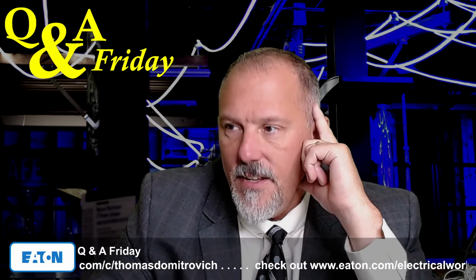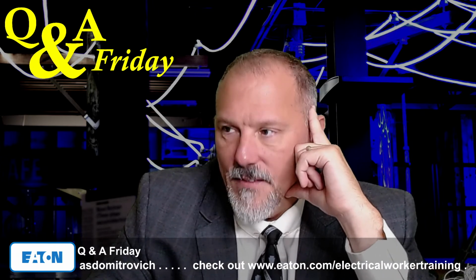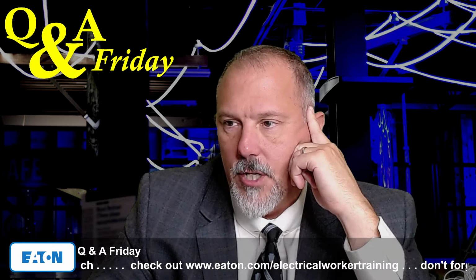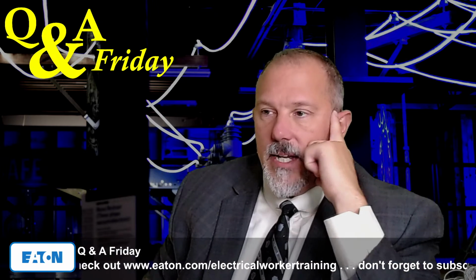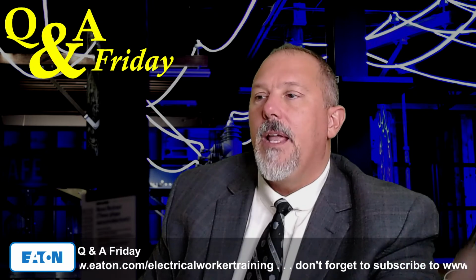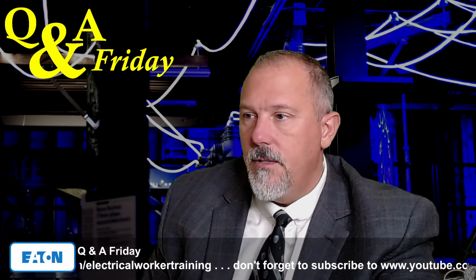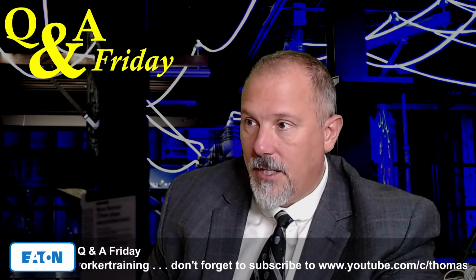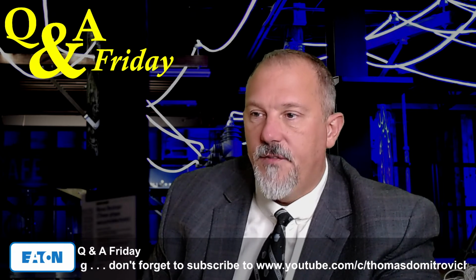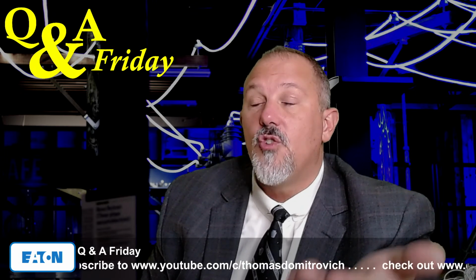I have a question on the compatibility between the GFCI requirement and the AFCI requirement in the National Electrical Code. In general, when it comes to protecting from both a shock hazard and an arcing fault fire hazard, like in a kitchen, what is the typical circuit configuration that satisfies both 210.8 and 210.12? Are there any listed products combining AFCI and GFCI technologies in the same breaker or receptacle?